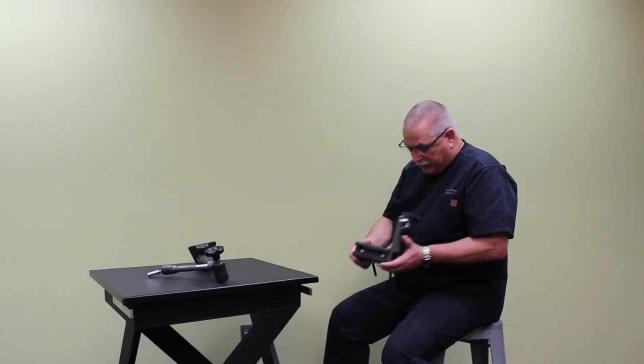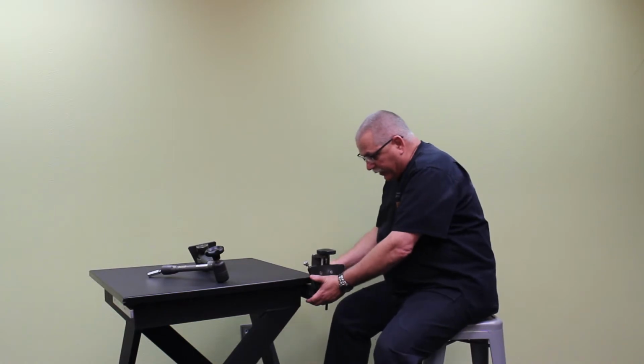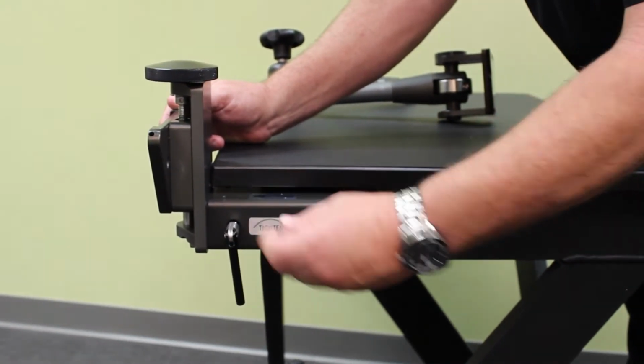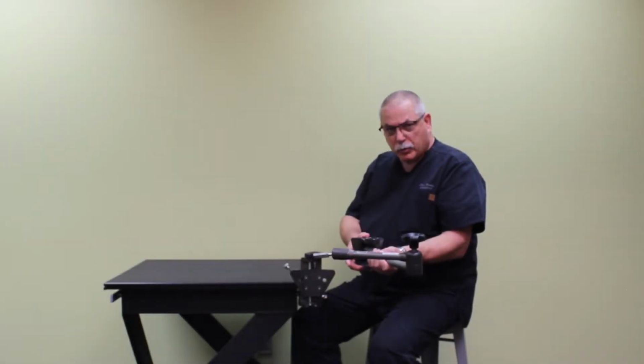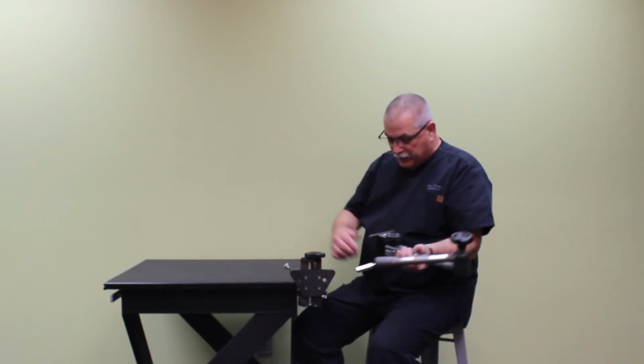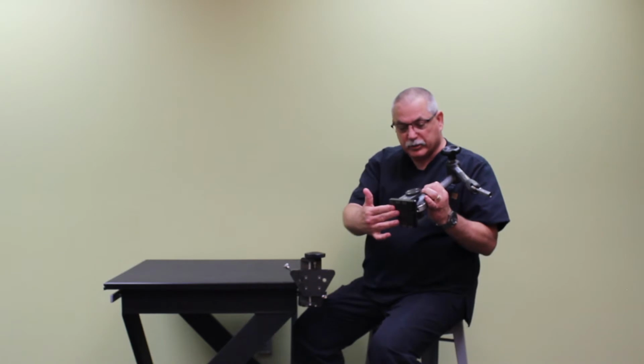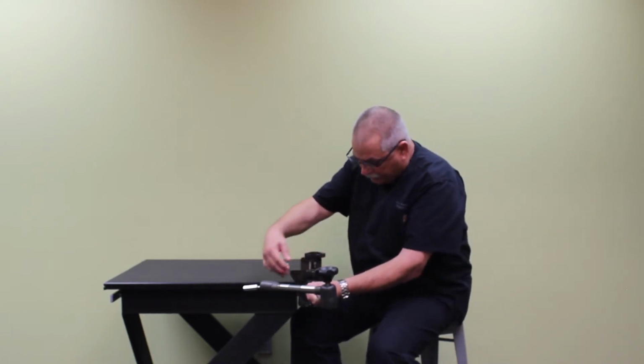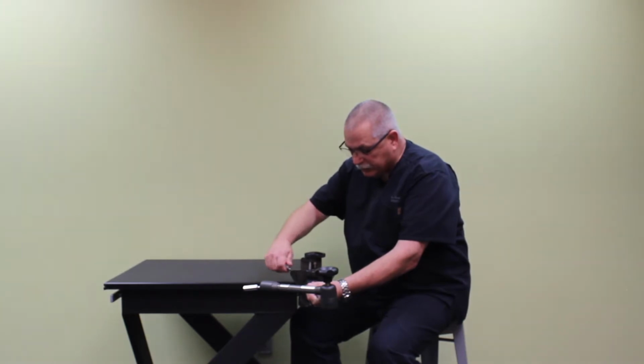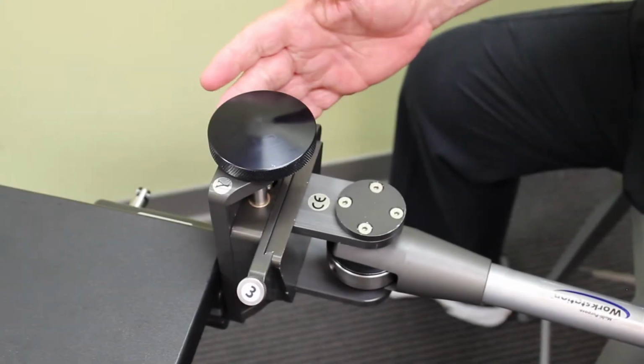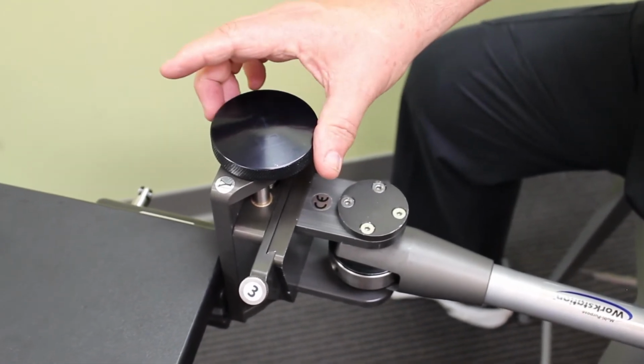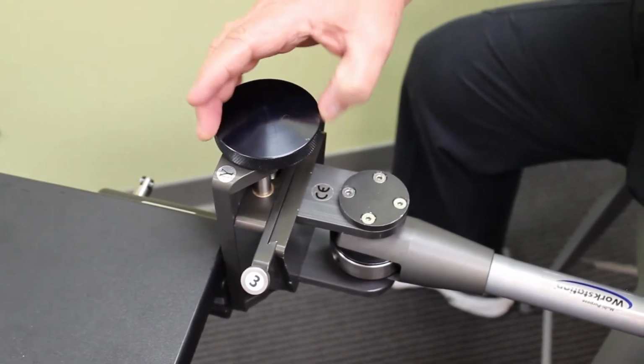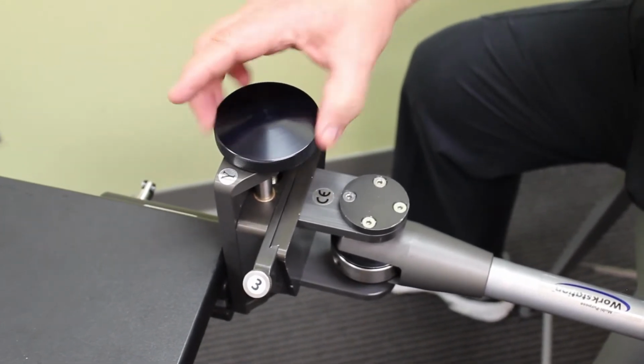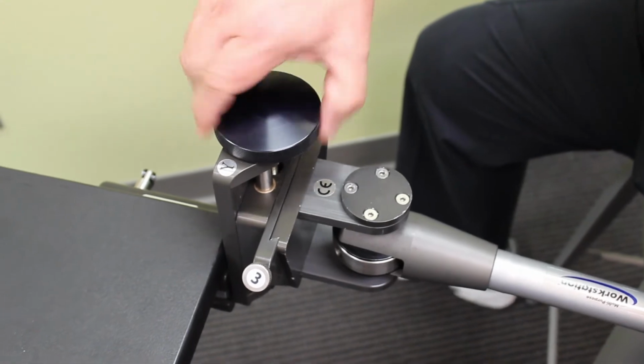To attach the rail mount for the multi-purpose workstation LP configuration, just take the mount, slide it onto the rail, and then tighten. And then you're ready to go. To attach the adjustment arm of the multi-purpose workstation LP to the rail mount, just simply look for the triangular shape here, the triangular shape here, place it inside, and then tighten the screw here, and it's ready to go. To make vertical adjustments on the multi-purpose workstation stabilizer, simply turn this knob where it attaches to the table. Counterclockwise will lower the arm, clockwise will raise the arm.